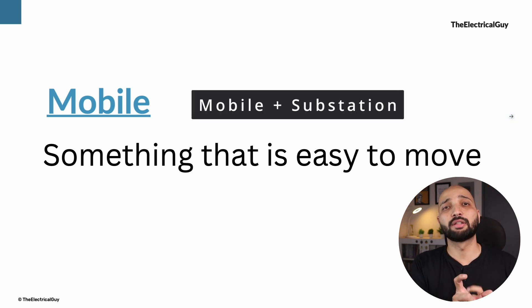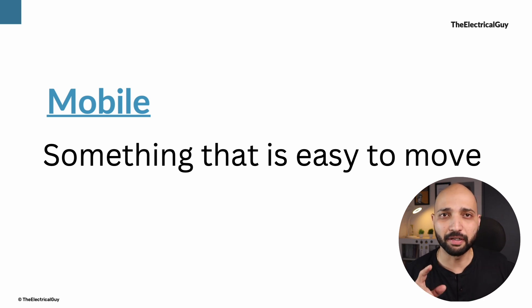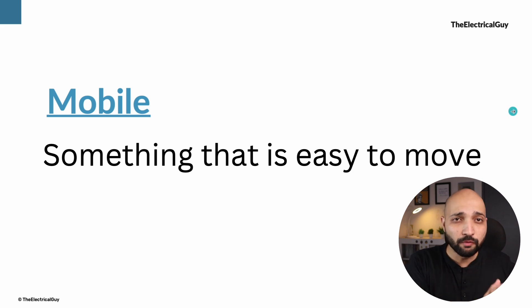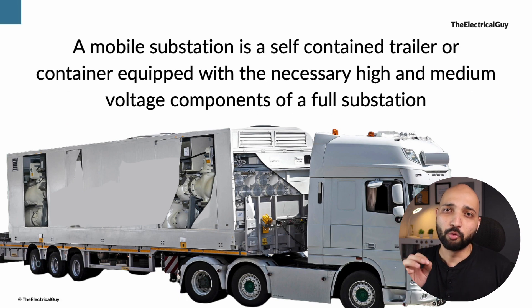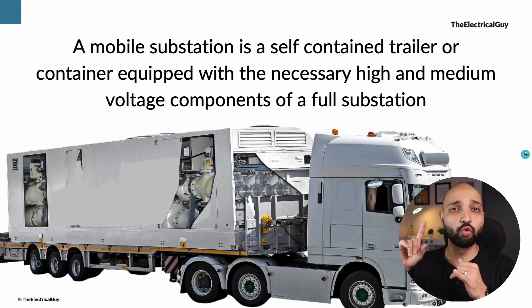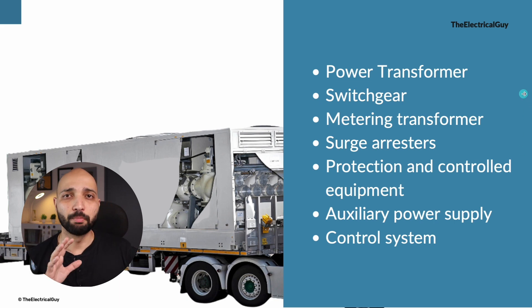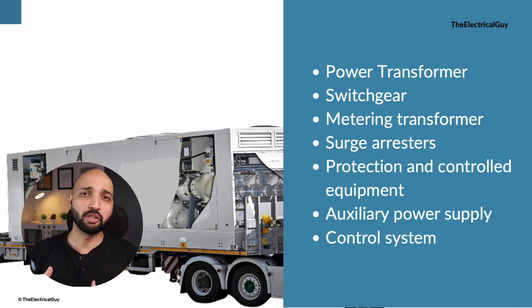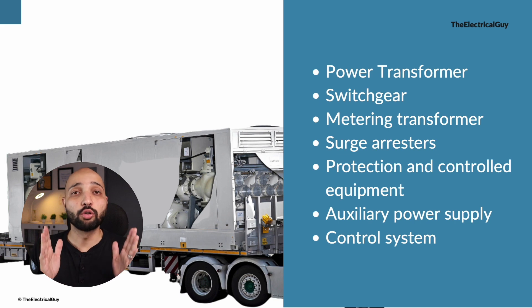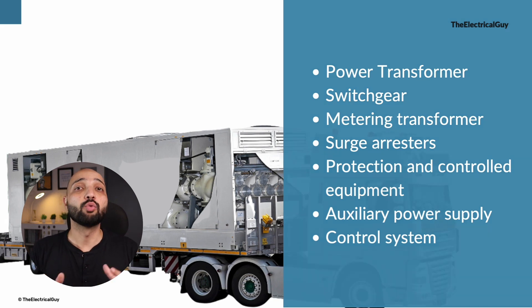So when we add the word 'mobile' with 'substation', does it mean it can be controlled by a mobile device? No, it does not. A mobile substation means a substation that can be moved easily from one place to another. It is a self-contained and autonomous system mounted on a trailer or container, equipped with necessary high and medium voltage components — power transformer, switchgear and disconnect switches, metering transformer, surge arrestor, protection and control equipment, and AC and DC auxiliary power and control systems.